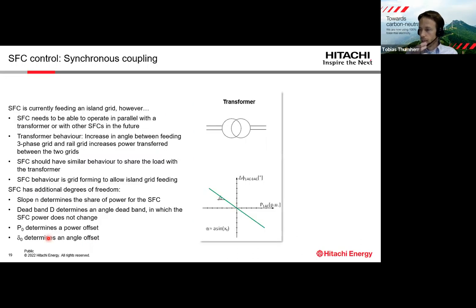So going more into details about these project challenges, I would like to start with control. As mentioned, the SFC has to be able to feed an island grid and also be able to operate in parallel with a transformer. And for that, we need to have a grid forming behavior of the static frequency converter. So basically, it's not operated as a current source, but rather as a voltage source. And if we look at the parallel connection with the transformer, it's important to understand how a transformer behaves. Basically, it's mainly inductive impedance.